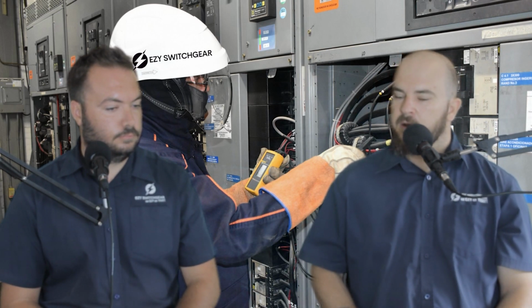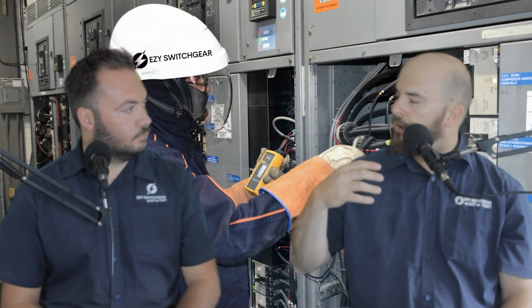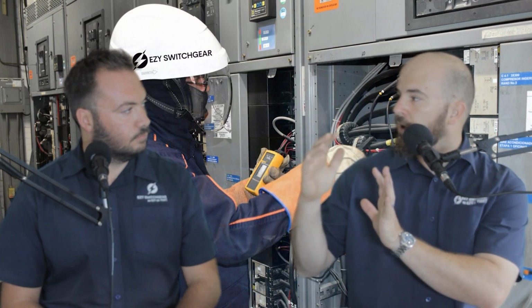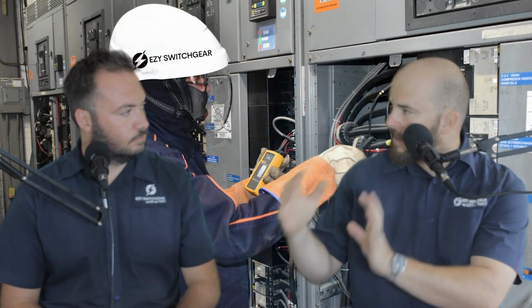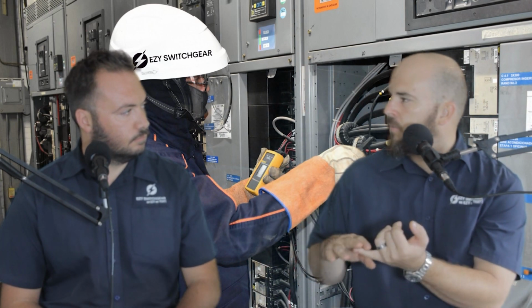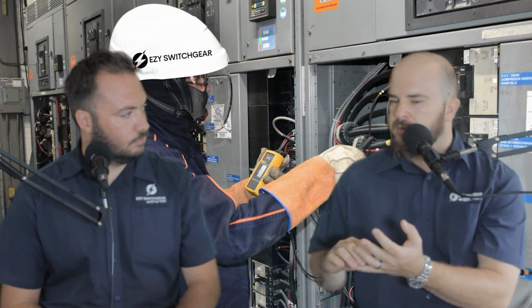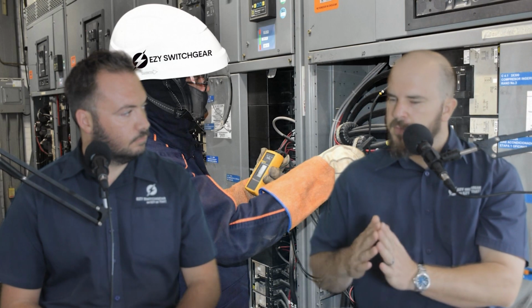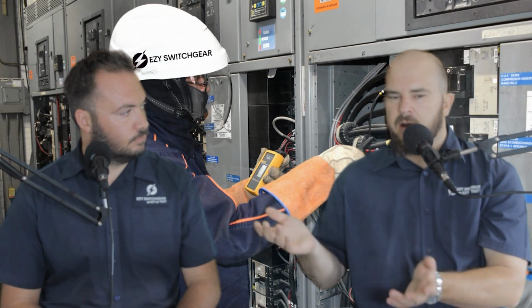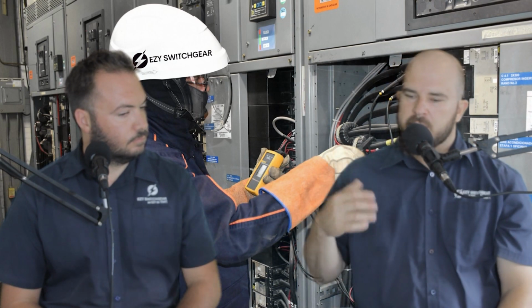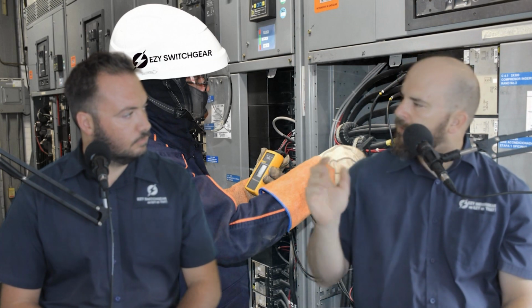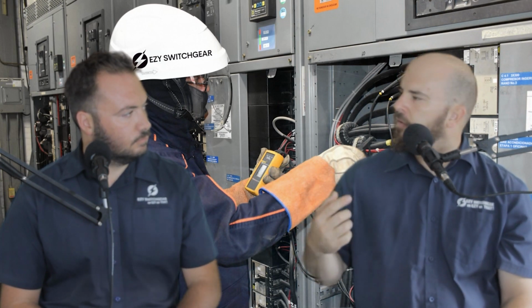Most of the time, the first line of defense would be to have good switchgear with inherent safety features such as AFLR, which is your arc flash safety. A is authorized persons, F is front, L is lateral, and R is rear. So if you have AFLR, it doesn't matter what happens, if you are around it, you will be safe.